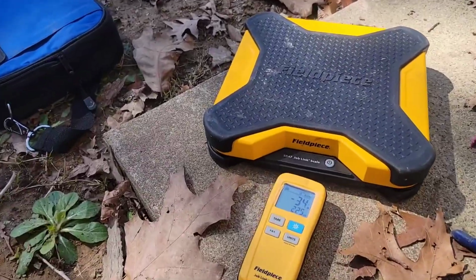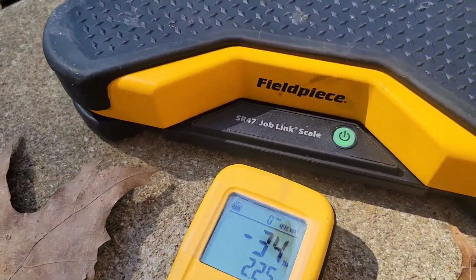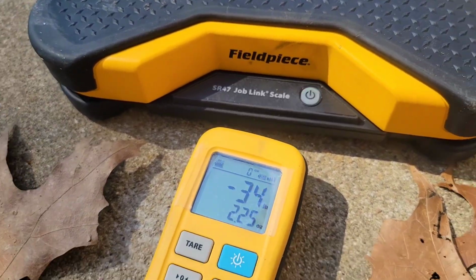Okay. No leak found right now with the leak detector or visually, so I'm going to bring back some nitrogen. I'm going to pump the refrigerant down into the outdoor unit, and then I'm going to pressure test the indoor coil first. And if I don't find it there, then I will probably recover the refrigerant and I'll pressure test the outdoor section so I can try to find that leak. I'm going to talk a little bit about the components of the outdoor unit, and then I'm going to probably end this video. Just in case you needed to know what scales I use, Fieldpiece SR47 Job Link scale.